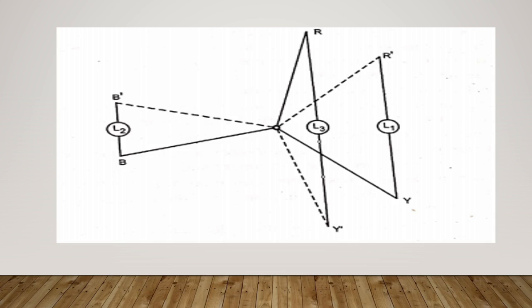So what are these potential transformers doing here? Potential transformers are connected directly across the switch, and the lamps are in the secondary circuits of the potential transformers. But in most installations there will be potential transformers connected across the line on both sides of the paralleling switch.